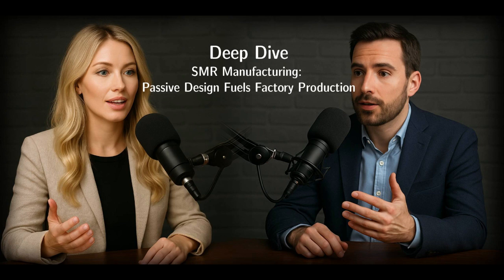What about the specific materials needed for these advanced reactors? Are they exotic? And once these components are built, how do you actually move these massive yet modular pieces? Yeah, the materials are definitely specialized. They have to be for a planned 60-year plant lifetime. But the transport challenges, believe it or not, they've largely been solved by other heavy industries already. Okay, so what kind of materials are we talking about? For the primary reactor parts, you're looking at things like SA508 Class 3 and SA533 Grade B Class 1 steels for the pressure vessels. For steam generator tubing, it's often Inconel 690, specifically chosen for its superior resistance to corrosion under harsh conditions.